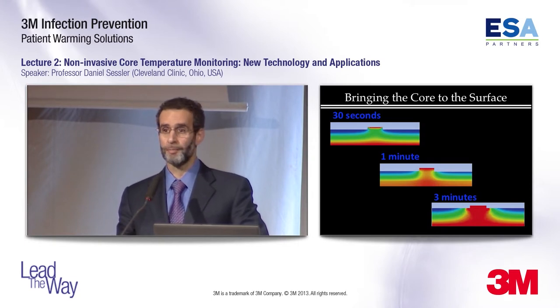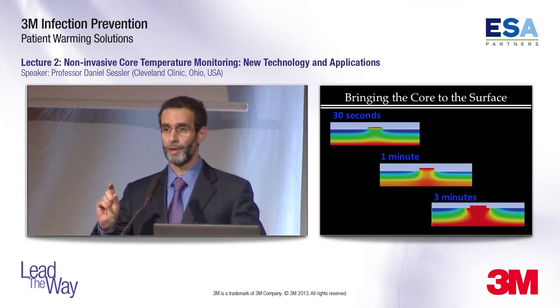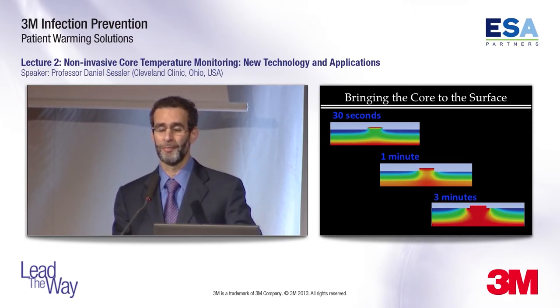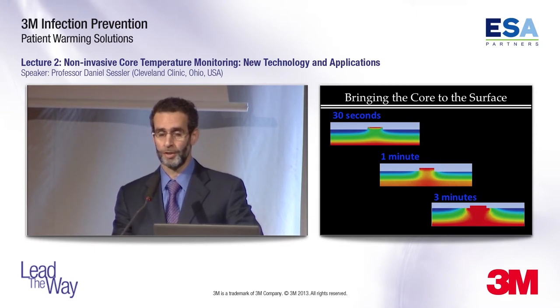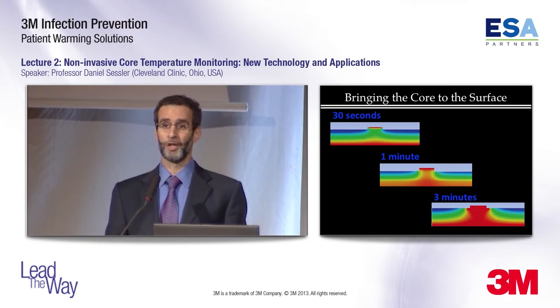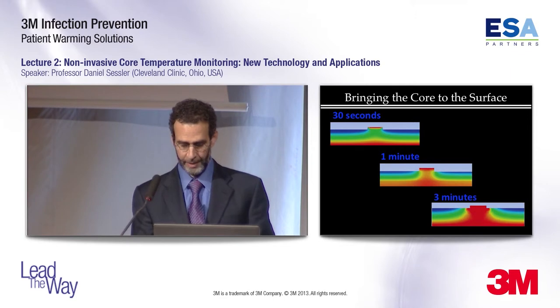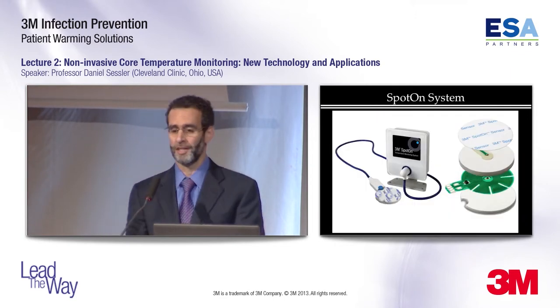The concept is well established — we and many others have tested the general concept of zeroing heat flux; it's called a zero heat flux thermometer. We and others have tested this extensively over the years, and the concept works extremely well. The question, of course, is whether the current device works, and the answer is yes.